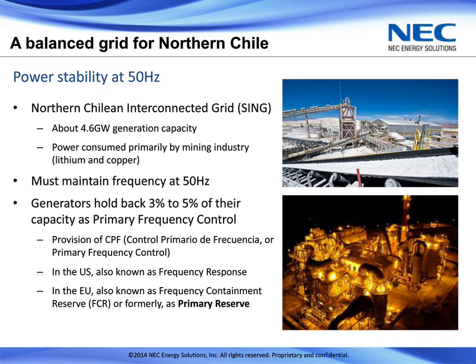Generators there typically hold back between 3 and 5% of their capacity to provide a service known as primary frequency control in that region. Just as a note, so people can put this in perspective, the United States calls this service frequency response, and in the EU and other parts of the world, it's known as primary reserve or frequency containment reserve.